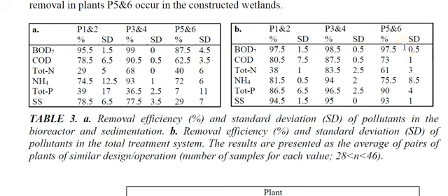The main difference, where we see the largest effect of adding the wetland, is in phosphorus, where in the best case for the bioreactor we reached 39% removal, while after adding the wetland, we reached 86%. In the case where we had 36, we reached 96, and the lowest was 7. And in the case with the least in the reactors, we still got 90% in the total.